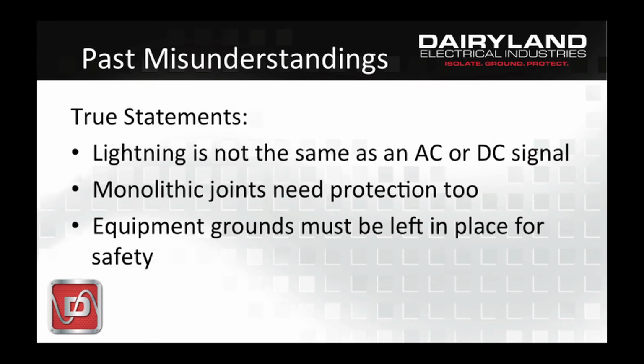Lightning is not the same type of signal as AC or DC. It has to be treated differently because it's a very different waveform and it produces different effects. Regarding insulated joints, some think of monolithic joints as the ultimate protection, and they are very good insulation systems, but they will fail if you provide enough voltage across that joint insulation. So they need protection as well.